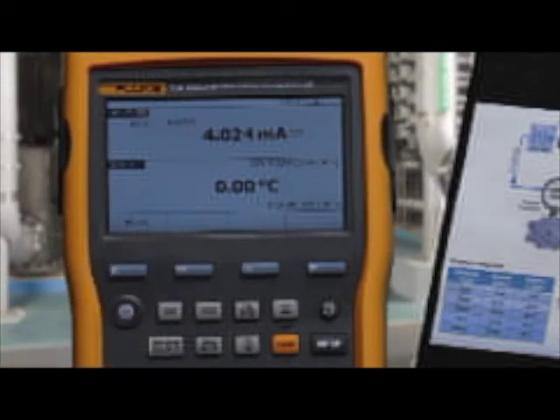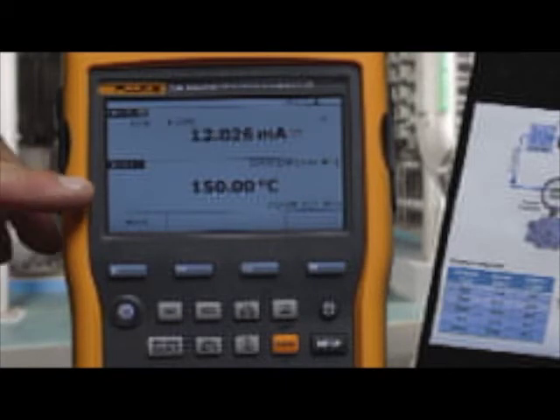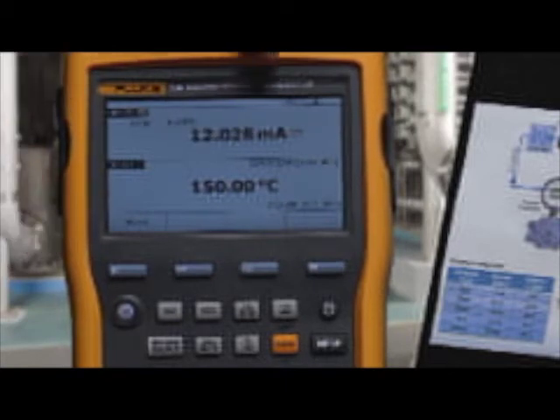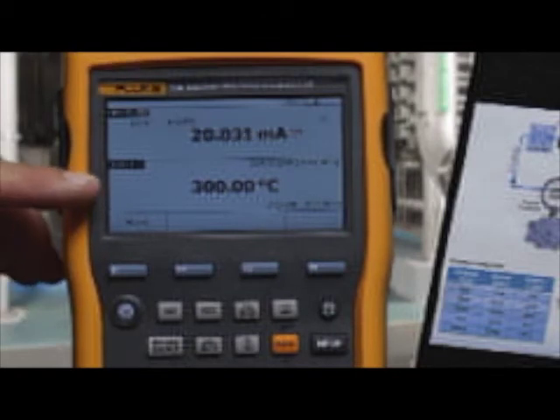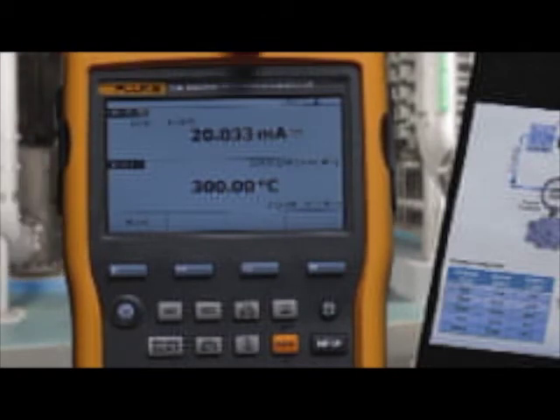At 0 percent, 4 milliamps is being measured, error percent is being calculated. The 50% value is applied, milliamp measured, and error percent being calculated. Then the 100% temperature value is applied, milliamp value is measured, and error percent is calculated.